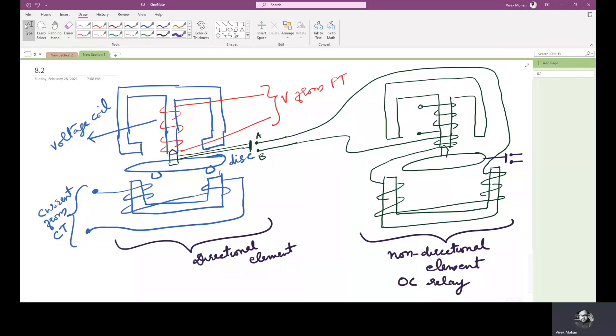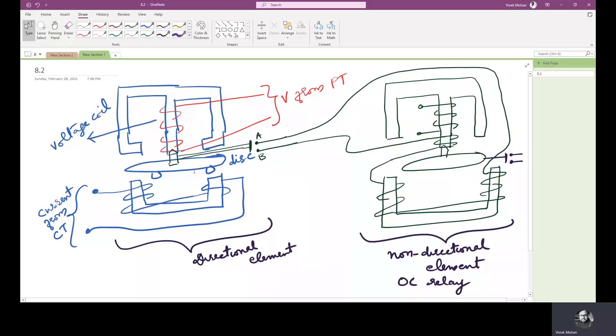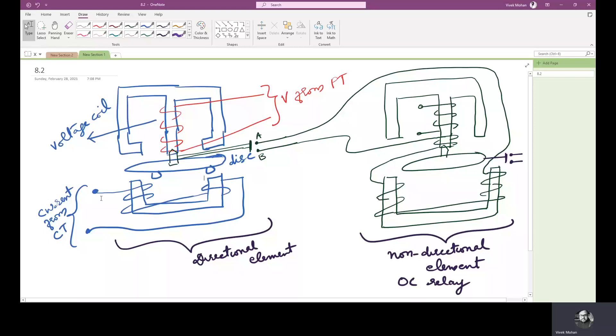The two fluxes φv and φi interact to produce the torque due to which the disc rotates and the trip contacts A and B are closed. The directional element is designed to be very sensitive — even though the voltage falls under short circuit, the current coil produces sufficient torque to have disc rotation. Even if the voltage coil does not produce the required flux, the torque produced by the current coil is sufficient to rotate the disc, so A-B will be closed and the second non-directional circuit will be active.